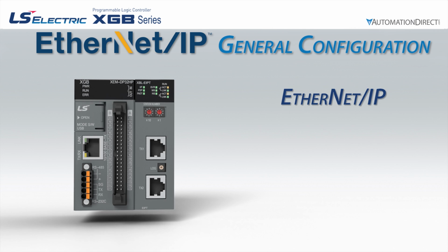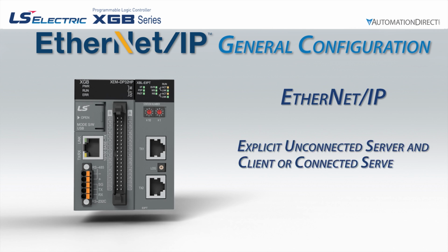This module will support unconnected server and client, and connected server only, explicit messaging as well as implicit messaging. The PLC can act as both an explicit client or server, as well as an implicit scanner or adapter.